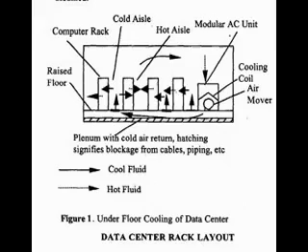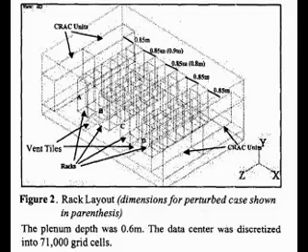The cooling load on a computer room air conditioning (CRAC) unit compared to its conventionally sized capacity will be referred to as the provisioning of the unit in a data center environment. An under-provisioned CRAC unit would indicate that the cooling load is higher than the capacity of the unit, while an over-provisioned CRAC unit would signify that the load is well within its capacity. The hypothesis is that malprovisioning will lead to waste of energy, and a properly provisioned environment will lead to efficient use of energy resources.